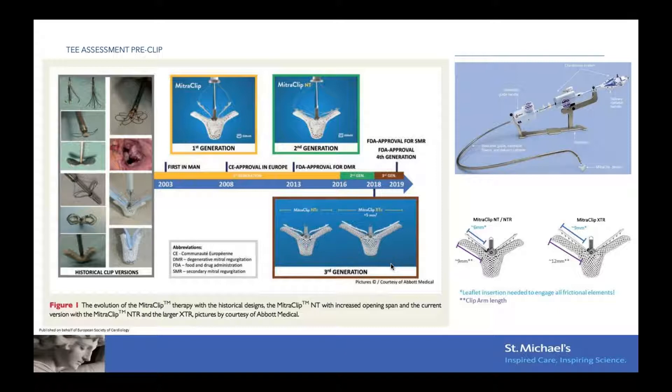Currently we use the generation three devices, which are the NTR and the XTR. Since December last year at St. Mike's, we also have access to the fourth generation clip, which are the NTW and the XTW — W stands for wide. That new clip has a width of six millimeters compared to four millimeters from the third generation, to allow bigger bites of the leaflets. The MitraClip is made of cobalt chromium and is coated with polyester to improve tissue healing, and it is MRI safe.